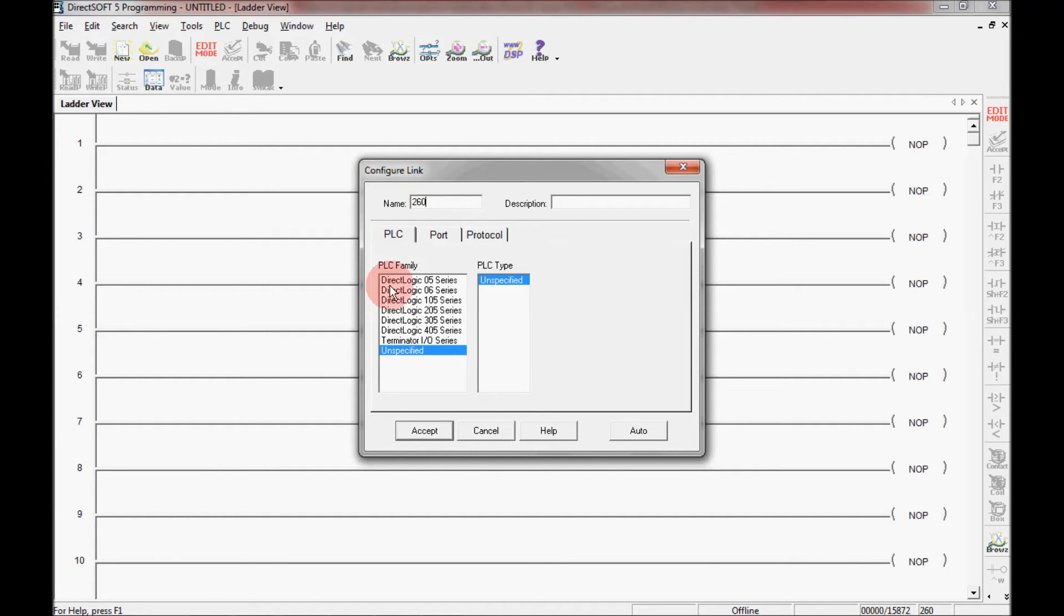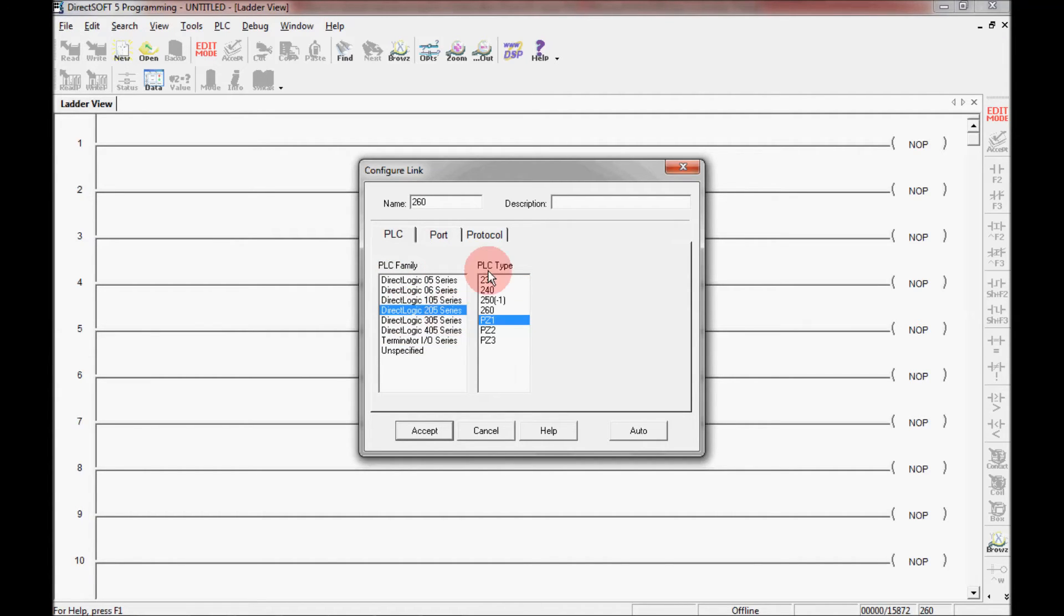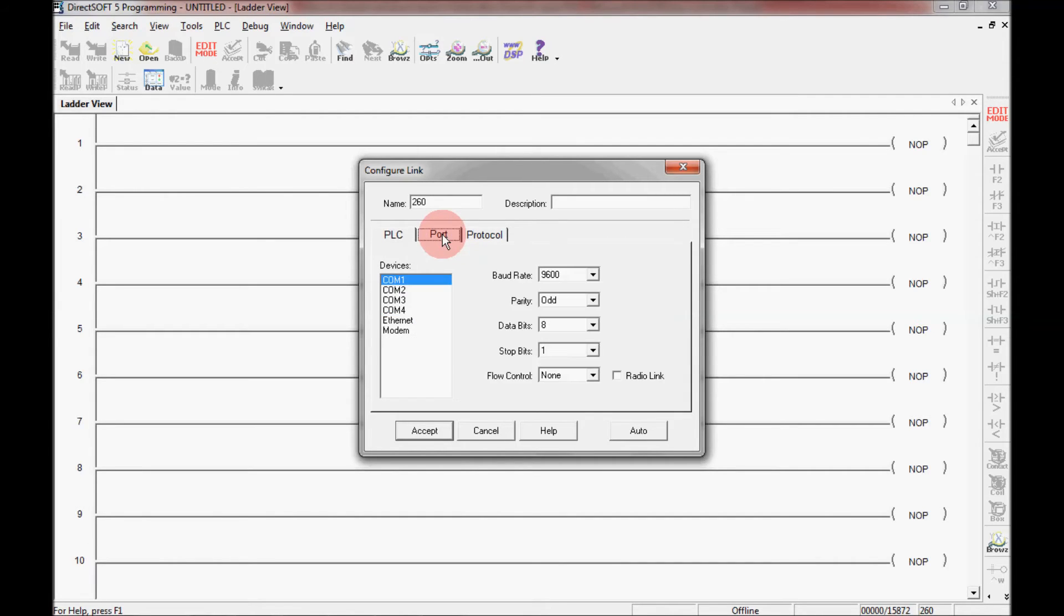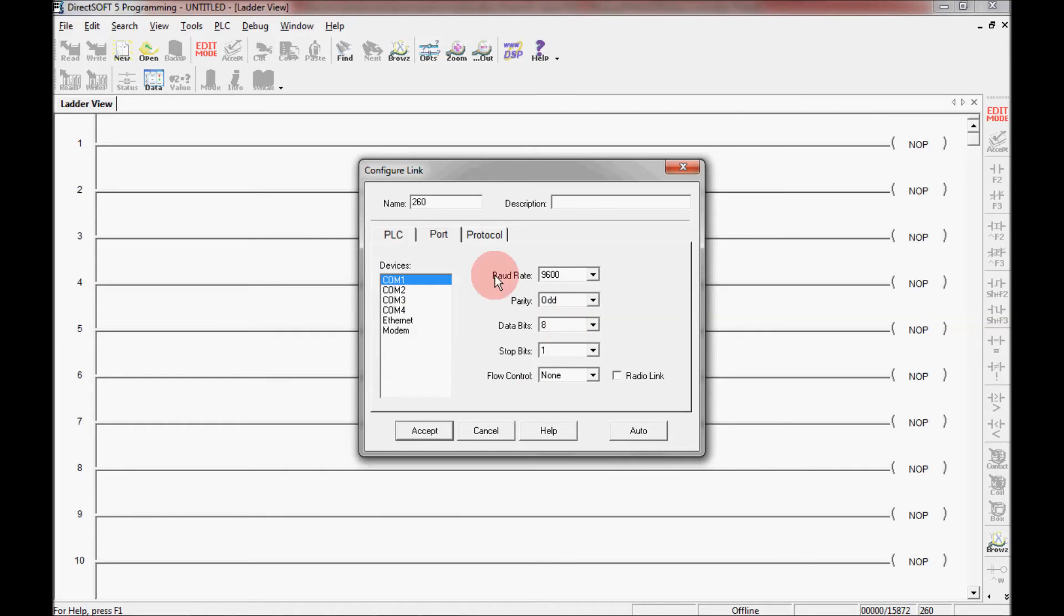Now I need to select a PLC family here, which is the DirectLogic 205 series. And the PLC type is going to be a 260 processor. And then under port here I'm going to click on this tab, and it's going to ask me which port do I have my programming cable plugged into, which is COM1. And I'm going to leave these baud rates as 9600 because the 205 supports only 9600 baud rate.